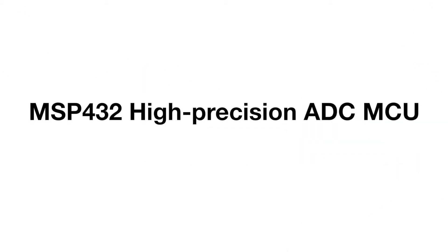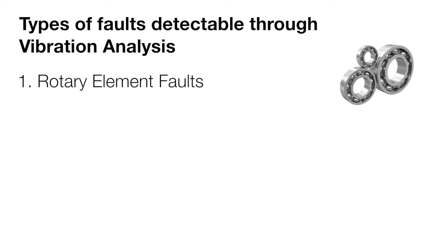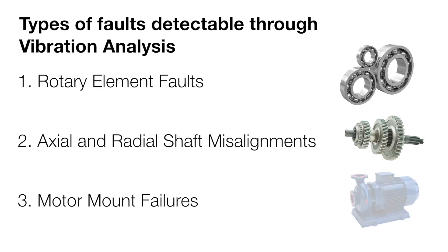Hello and welcome to the TI Reference Design for Vibration Condition Monitoring with the SimpleLink MSP432 P4 host MCUs. Vibration analysis for motors and pumps may be used to detect rotary element faults like those arising due to bearing defects and defects on the inner and outer races, faults due to axial and radial shaft misalignments, and failure of the motor mount at a very early stage.